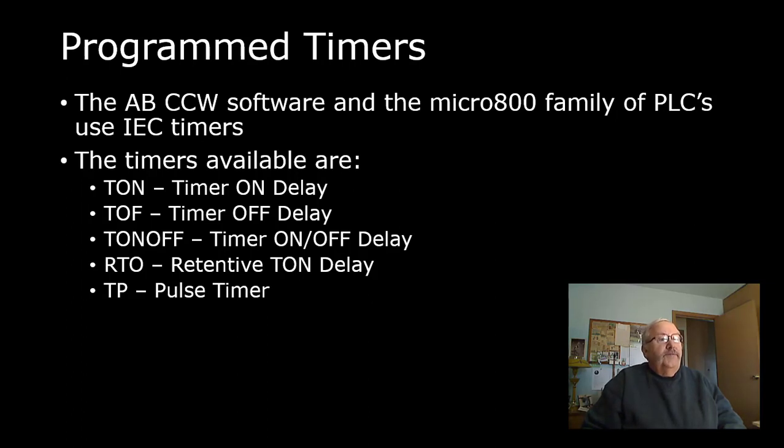Hi all, and in this video we're going to talk about the PLC timers that are available in the Rockwell CCW software. So if you take a look at it, it says that we have 5 timers available. We have a TON timer, which is a timer on delay, a TOF timer, which is a timer off delay. This series has a timer on off delay timer. There's an RTO timer, which is a retentive timer, and there's a TP, which is a pulse timer.